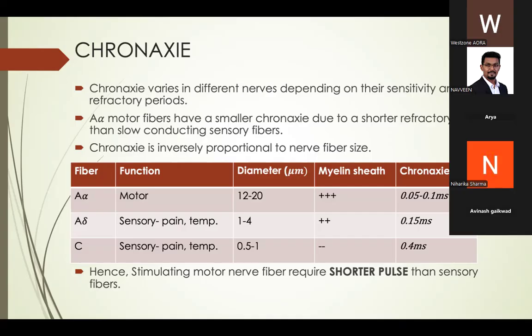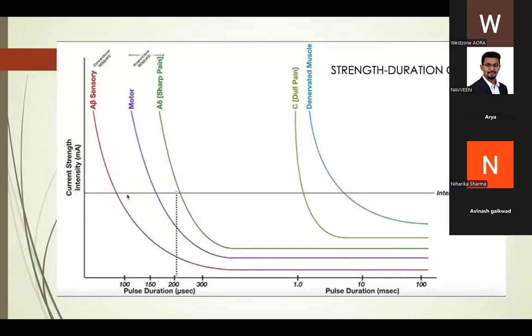The A alpha motor fibers have a diameter of 12 to 20 and are myelinated. They require a chronaxie of 0.05 to 0.1 millisecond. And A delta, which is a sensory fiber, again myelinated, requires a chronaxie of 0.15 millisecond. And C sensory fibers, which are unmyelinated, require a high chronaxie, which is 0.4 millisecond. And this is the strength duration curve. So as we can see, this is the motor, and this is the A delta, which is the sensory nerve fibers. So the motor nerve fiber will require a shorter chronaxie when compared to the sensory fibers.